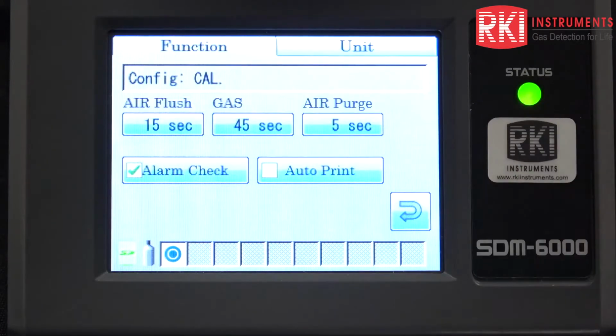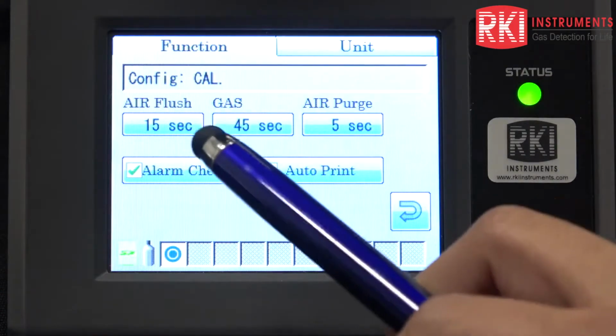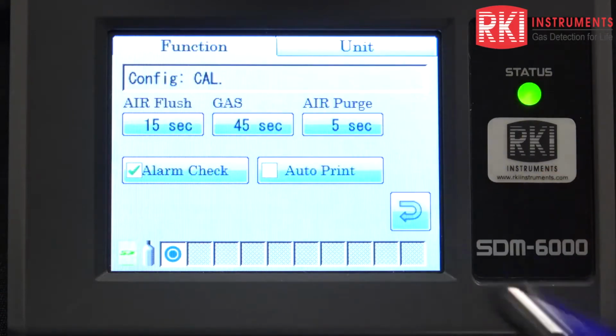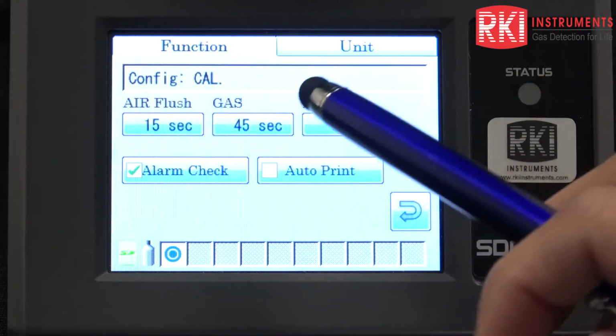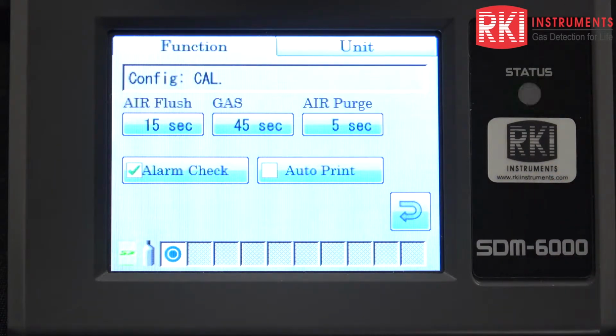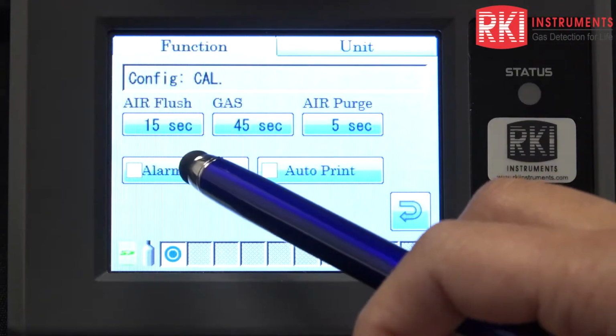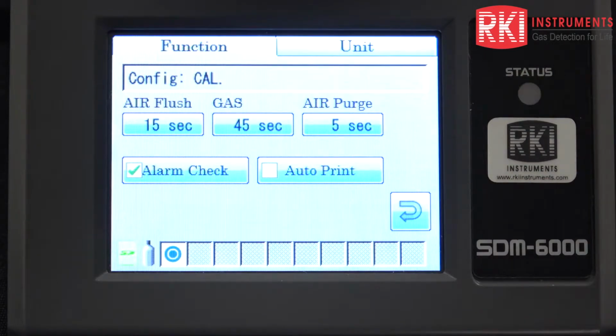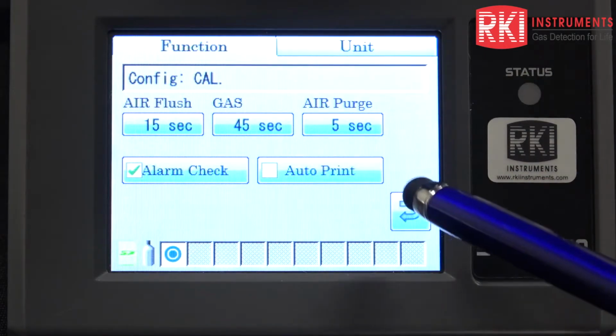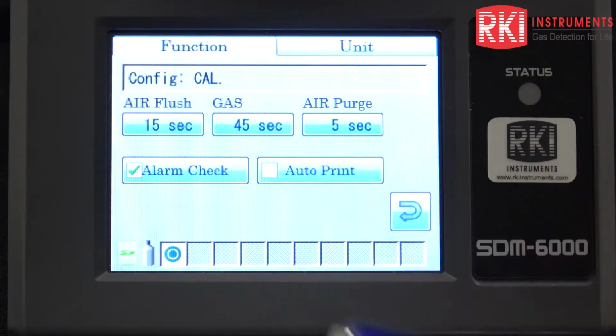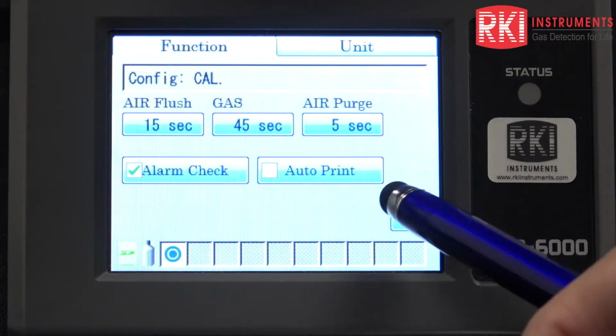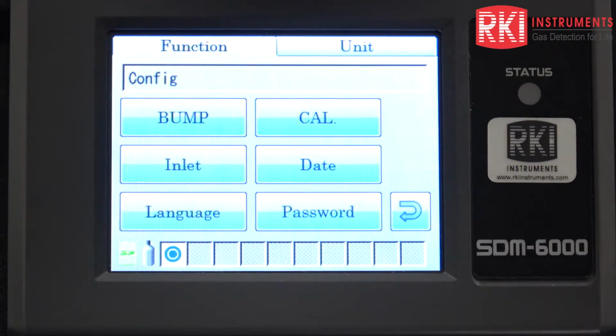Calibration parameters. There's a little bit less here, but it's the same type of deal. Air flush, gas, and air purge. So, air cal, the amount of time it runs the gas, and then the air purge, where it purges out and cleans the system out. Alarm check, same deal as with the bump test. It's going to perform an alarm check after calibration. I'm going to go ahead and check that. And auto print, you can check and uncheck it if you have a printer connected. I'm going to go back.